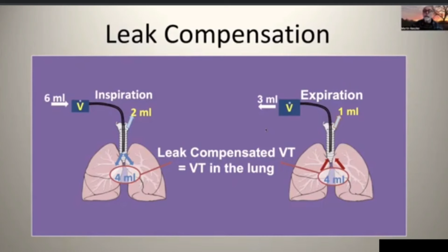This is not measured directly, but the Draeger ventilator can calculate this. There's usually also some leak during the expiratory phase, let's say 1 ml, it's typically less, so that the exhaled tidal volume might only be 3 ml. And if you're using that 3 ml in the absence of leak compensation on many other devices, then you would be underestimating what the patient's actually seeing. So a large leak around the endotracheal tube used to be a contraindication to volume guarantee, but it is no longer with the modern device, with the VN500 and later, because this really effective leak compensation maintains a constant tidal volume despite progressively larger leak.